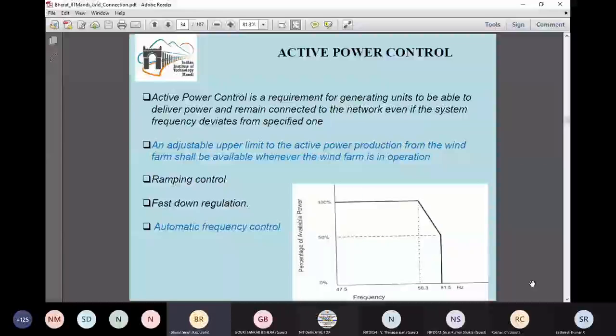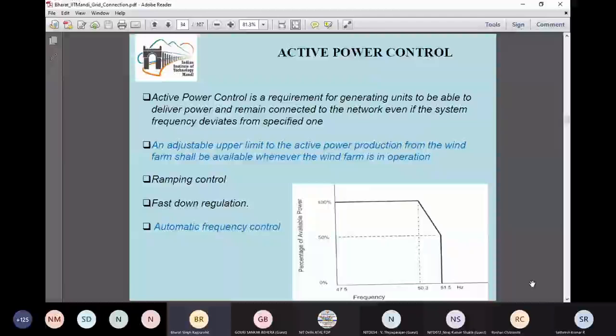Yes. So this is the first grid connection requirement we can discuss here. The first grid connection requirement is about the active power control. The meaning of active power control is that for the active power, or the real power, produced by the renewable energy sources whenever it is getting fed into the grid, a control should be available with the operator. This is generally known as an adjustable upper limit available with the operator, so that the operator is able to change the power which is getting fed into the grid. Fine. So this is a need to be addressed.